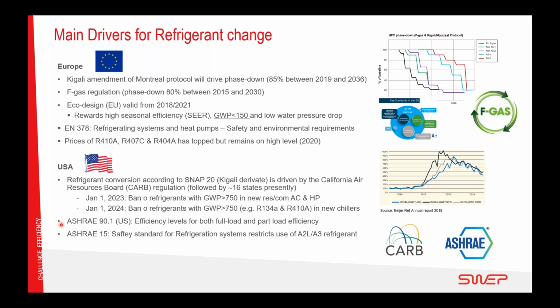2024, there will also be a ban on refrigerants for GWP above 750 in new chillers. And this will drive the change for low GWP refrigerants. Efficiency is governed by ASHRAE 90.1, both full load and part load efficiency. And ASHRAE 15 is the safety standard for refrigeration system, and that restricts the use of A2L and A3 refrigerants. That means flammable refrigerants.